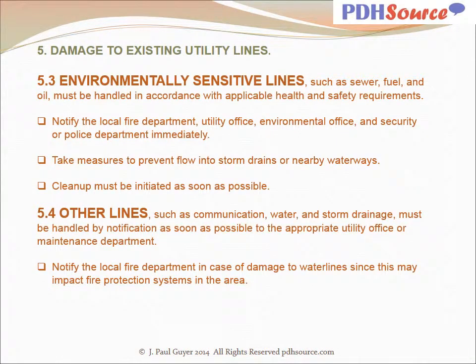Environmentally sensitive lines such as sewer, fuel, and oil must be handled in accordance with applicable health and safety requirements. Notify the local fire department, utility office, environmental office, and security or police department immediately. Take measures to prevent flow into storm drains or nearby waterways. Cleanup must be initiated as soon as possible. Other lines, such as communication, water, and storm drainage, must be handled by notification as soon as possible to the appropriate utility office or maintenance department. Notify the local fire department in case of damage to water lines, since this may impact fire protection systems in the area.